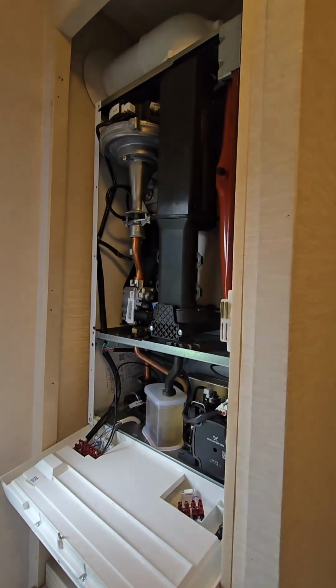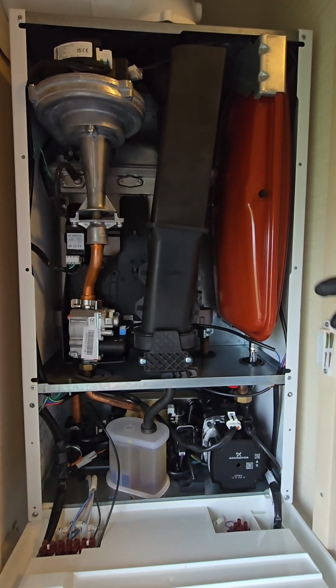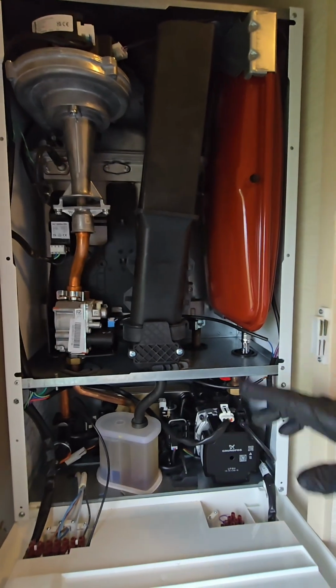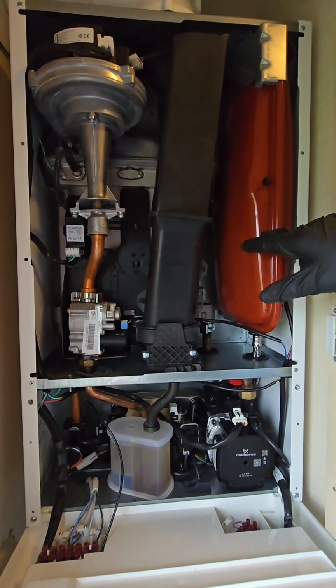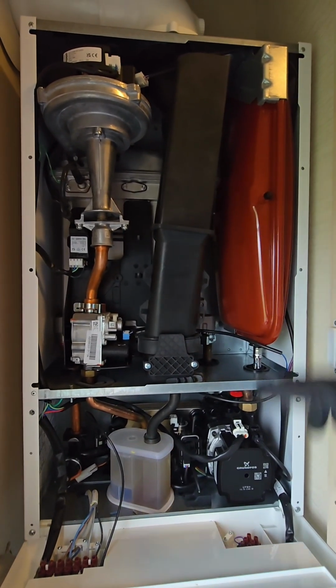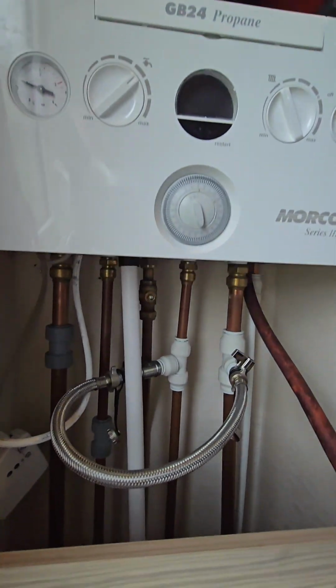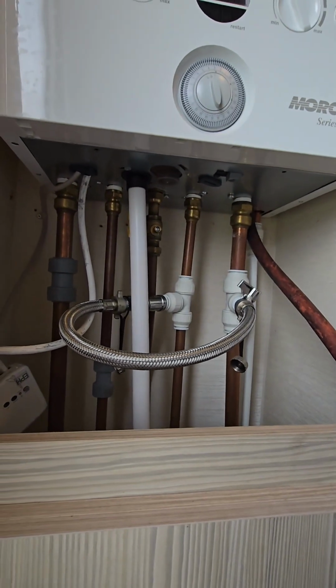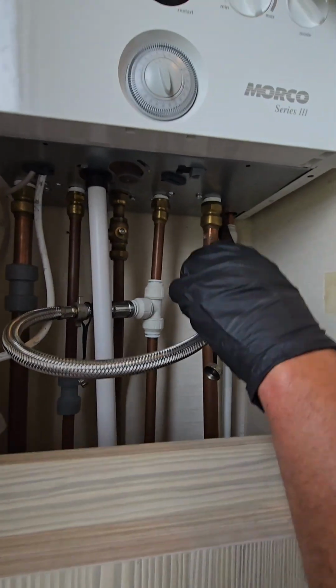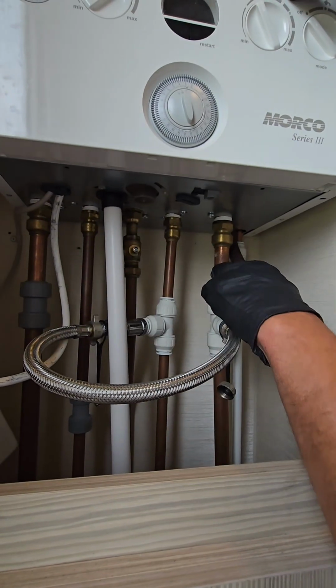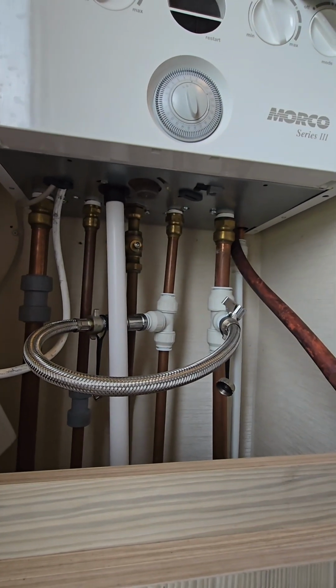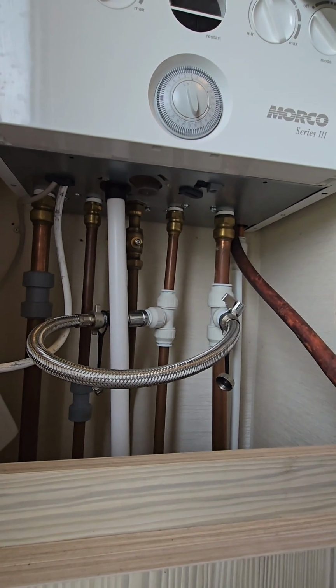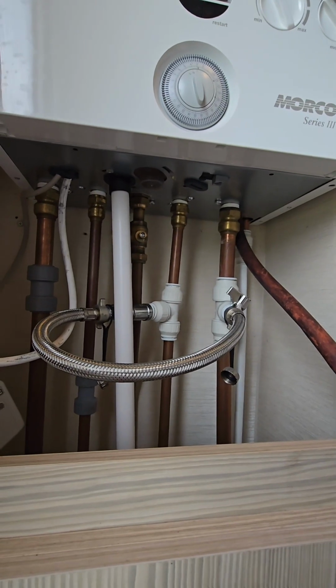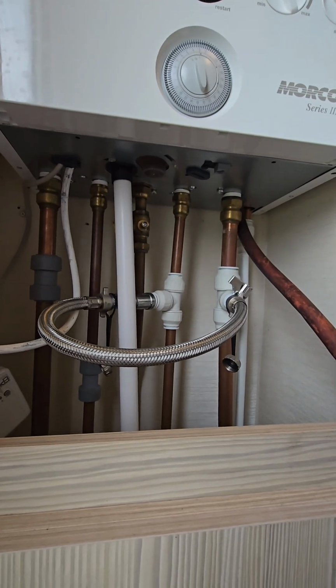Lift up like so. The first thing we're going to do is fully drain the appliance, deflate and recharge the expansion vessel. On most appliances we would have an isolation valve on the flow and return. However, this boiler is in a caravan and it is at the highest point of the system, so we don't need to isolate it.